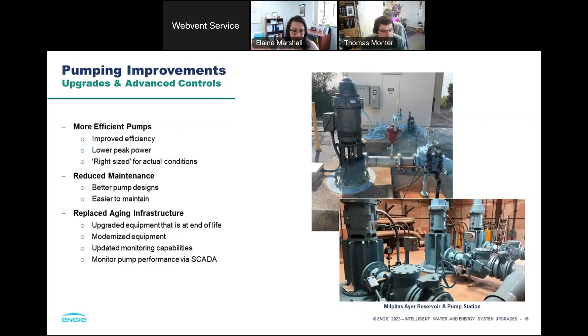The water treatment system had a lot of challenges because there was really no way to monitor these sites remotely. They were having to send staff up multiple times a week to monitor water quality. Especially during the summer, they would run into problems with bacterial growth, nitrifying bacteria in their tanks when the water temperature got warm, because they're using monochloramines at the site. Chlorine also offers issues during high temperatures, but a different set of issues.